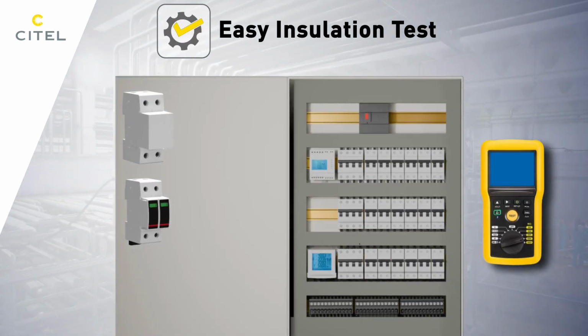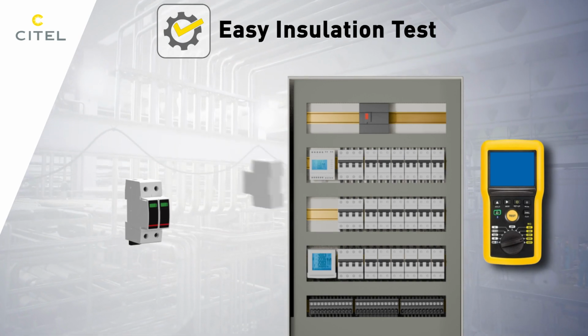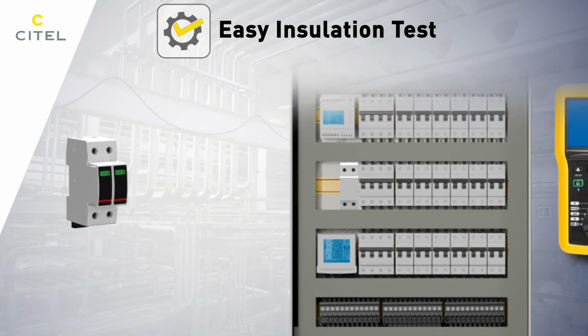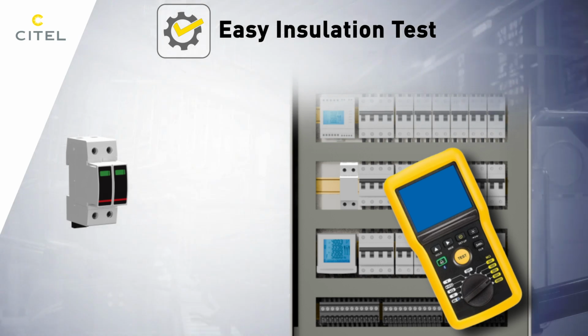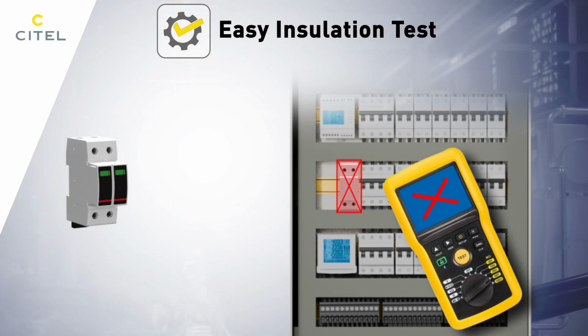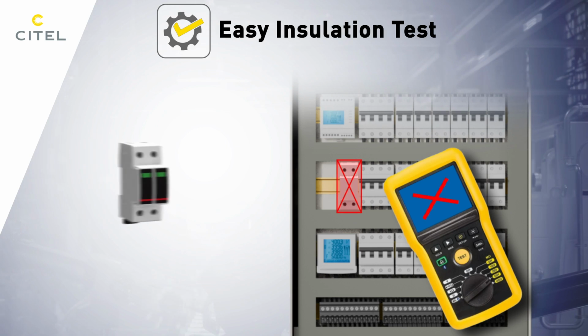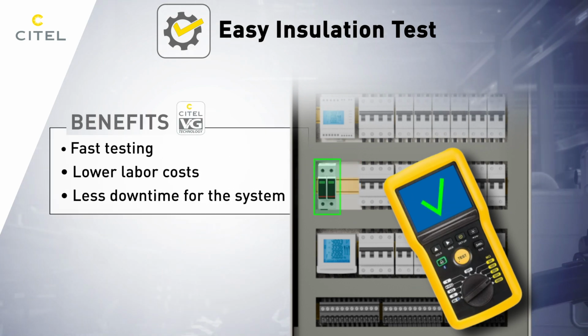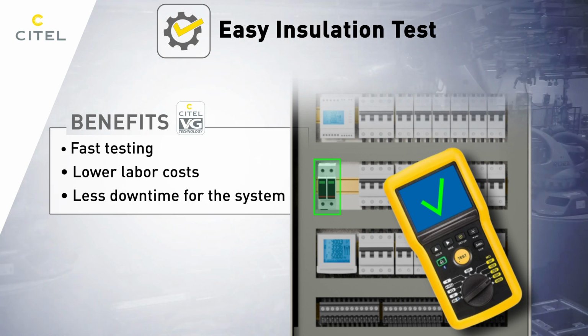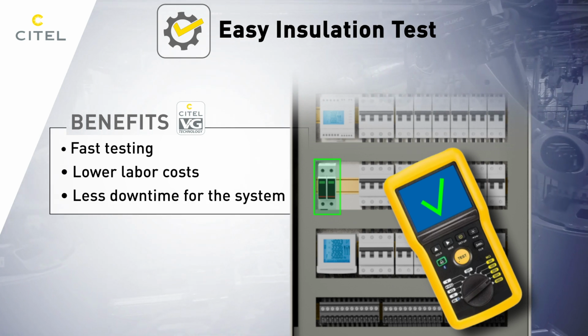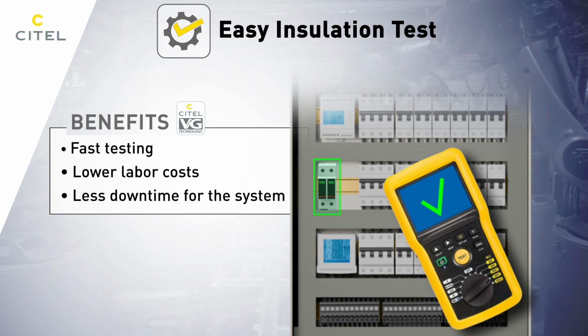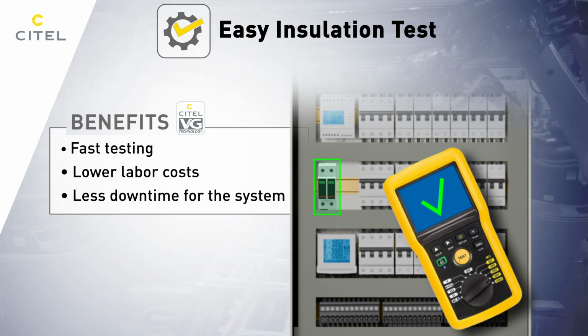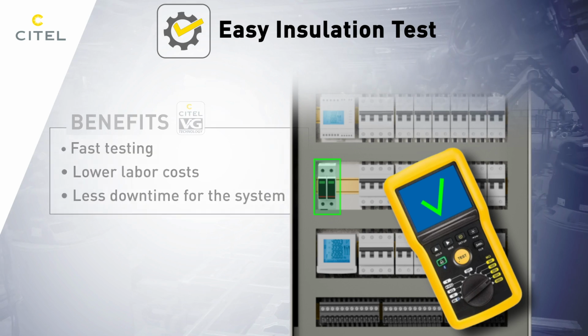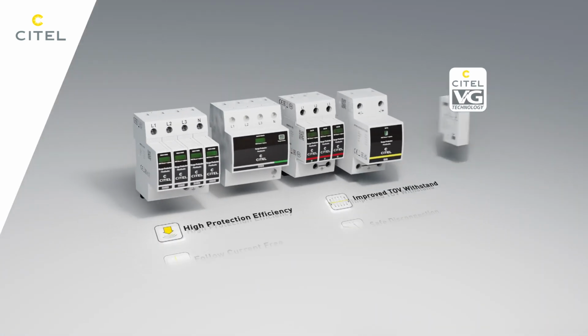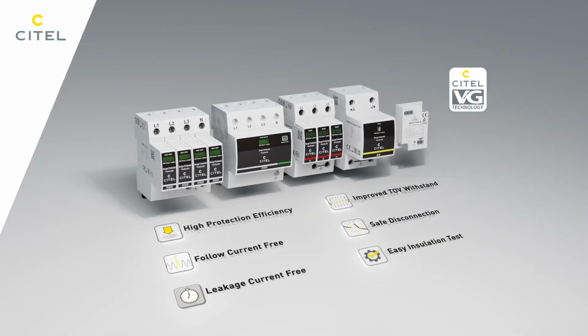Insulation testing is a standard part of any commissioning process. While traditional surge protection devices must be disconnected during these tests to prevent interference, SPDs with VG technology are allowed to remain connected to the electrical installation. The result? Faster testing, lower labor costs, and less downtime for the system, which is particularly important for large-scale installations or projects where time is a critical factor. VG technology, a smarter way to protect your equipment.